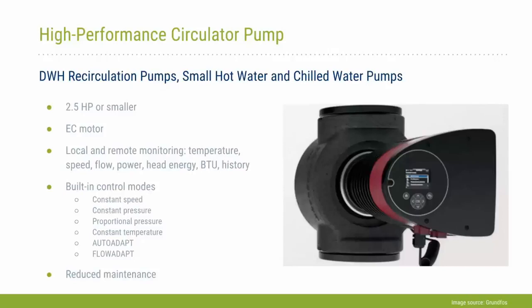And it has the ability to do local and remote monitoring of all of the operational characteristics of the pump. So you're able to monitor things like pump power, BTUs of heat delivered, supply water temperature, pump speed. All of those things are actually built into the internals of the pump.